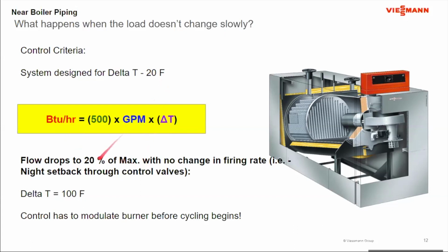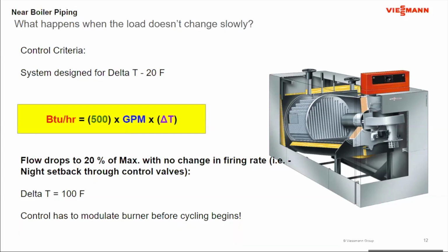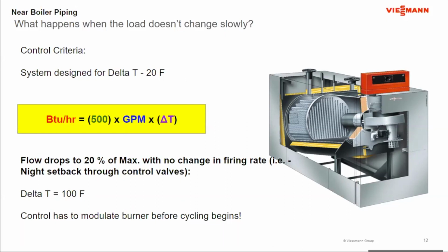to 20% flow, all of a sudden the boiler starts, the water temperature in the system starts to drive itself up towards 100-degree delta T, okay? And this happens very quickly, okay? Again, when we start to look at operation, when this kind of event happens, it depends on how quickly the system can respond to the change. The system may respond and be able to operate through modulation, or what may happen is it may be quicker than the integral, and all of a sudden the boiler has to start cycling to bring everything back into control again.